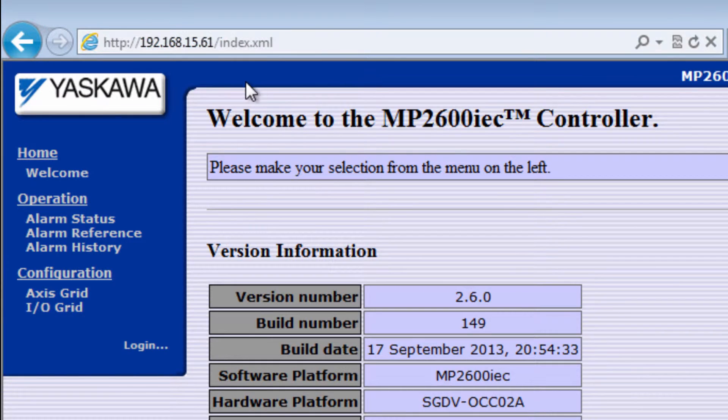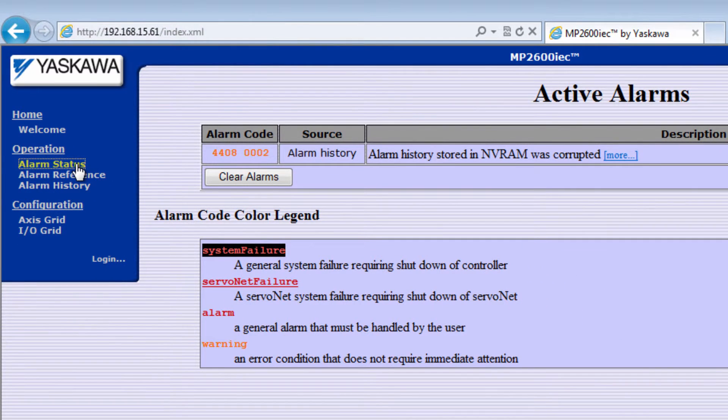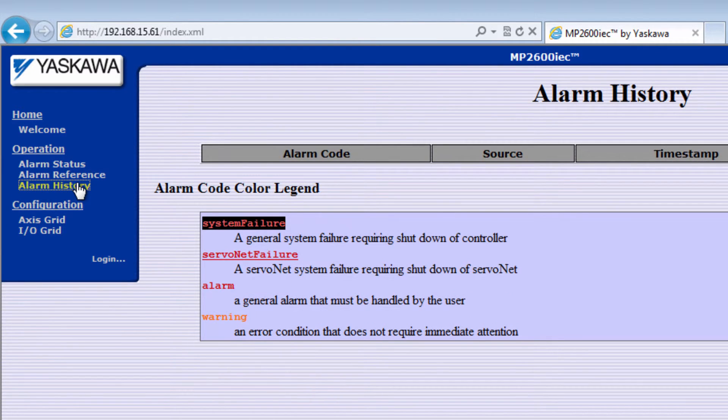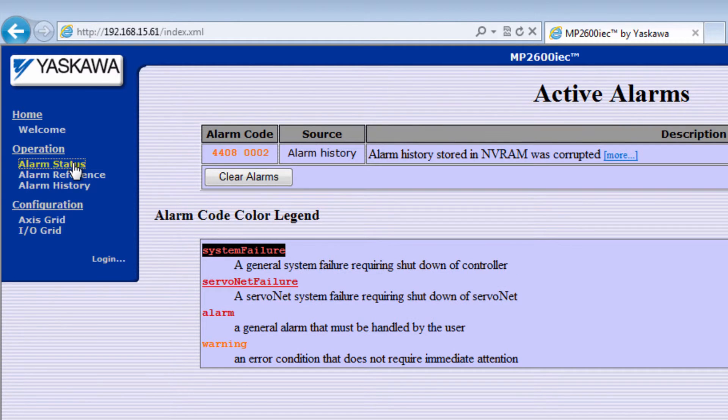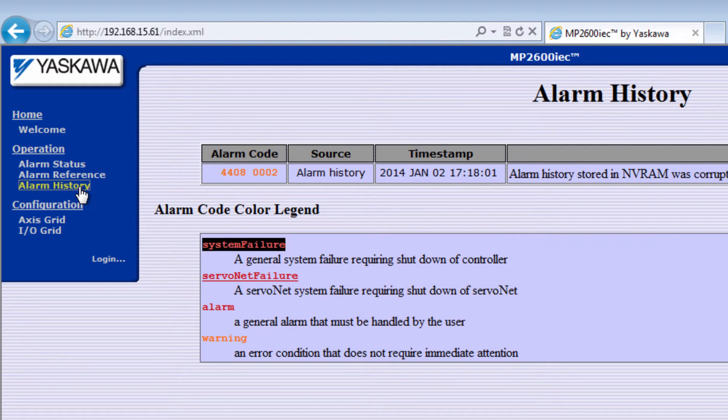The Alarm Status shows that the Alarm History was corrupted due to the SRAM initialization. A quick peek at the Alarm History shows it's blank. This Alarm can be cleared, and the Alarm is added as the first in the History.